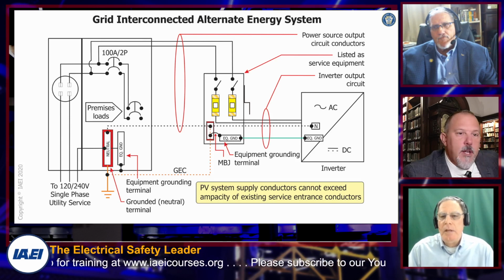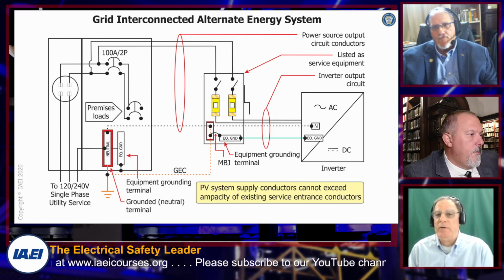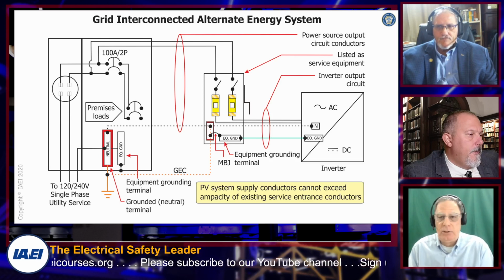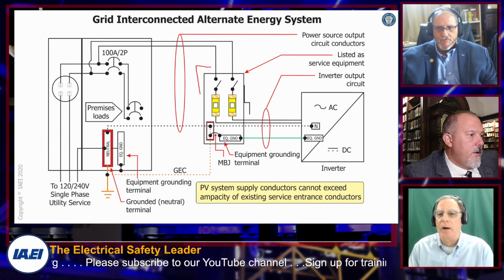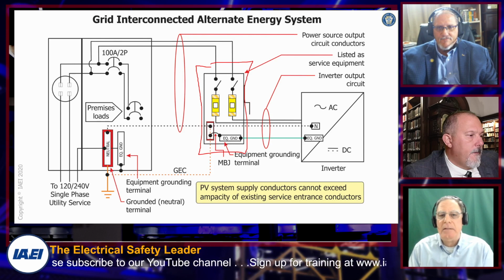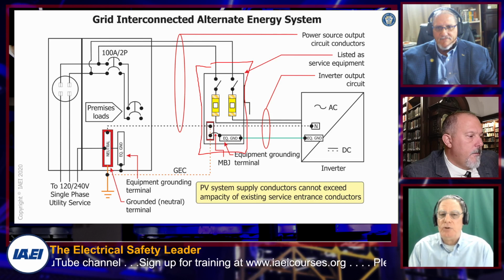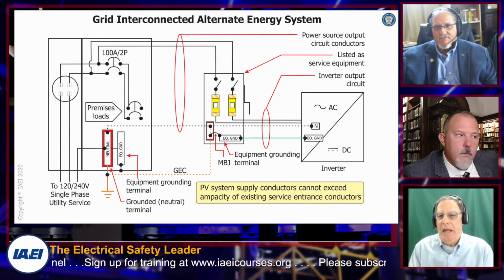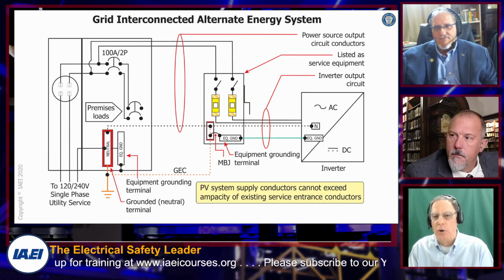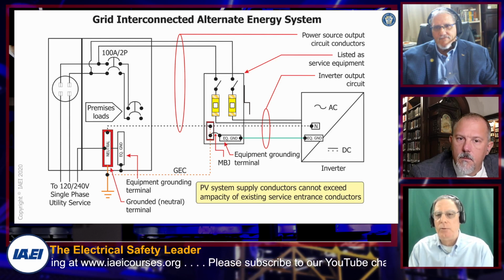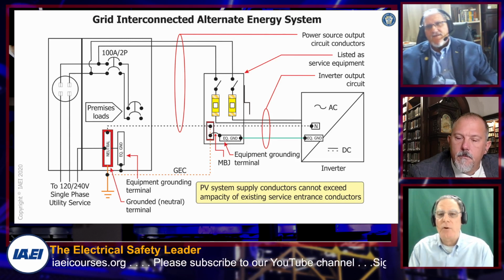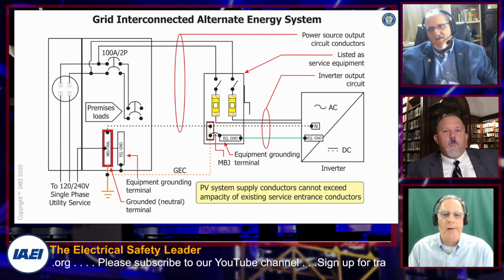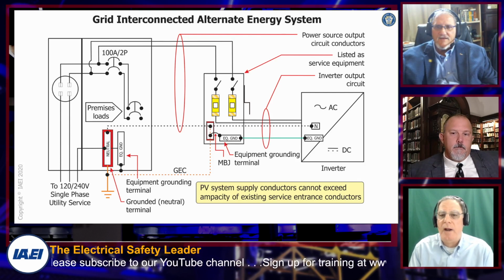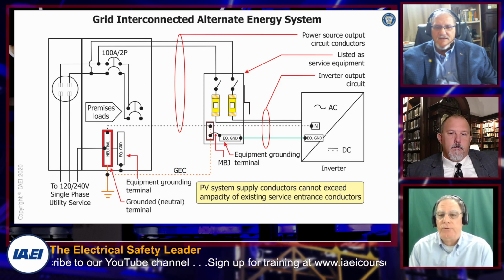That disconnect is treated just like a service disconnect. It isn't the service disconnect, it's not one of the six you're allowed to have, but you treat it grounding and bonding-wise just like a service, because in a ground fault situation at the inverter, it's going to act just like a load. The utility will still apply ground fault current as if it were a spa, a load, or another building, because the utility doesn't know that's an alternate energy system. It's just another place to dump power to.